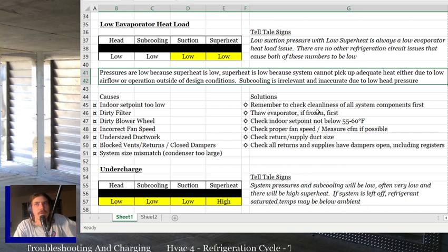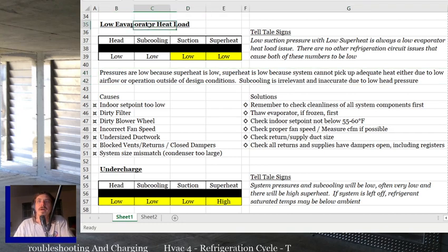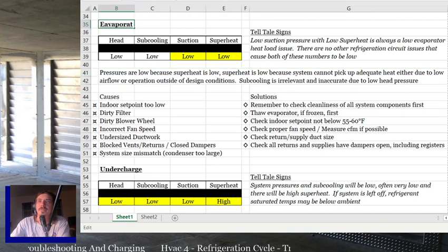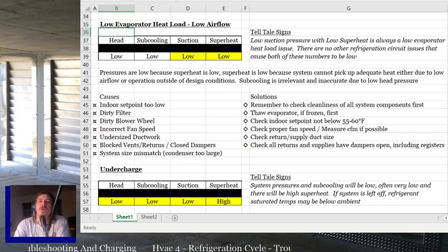So that's the reason I call it low evaporator heat load, but you might just want to think about it as what you're going to normally have. That's misspelled anyway, so fix that. You might want to just think about it as low airflow, because that's usually what it is. So if you got low evaporator heat load or low airflow in the evaporator, it's always low suction pressure, low superheat. Low suction pressure with low superheat is always low evaporator heat load. There are no other refrigeration circuit issues that cause both these numbers to be low. The pressures are low because the superheat is low. The superheat is low because the system cannot pick up adequate heat, either due to low airflow or operation outside of design conditions. Subcooling is irrelevant and inaccurate due to the low head pressure.